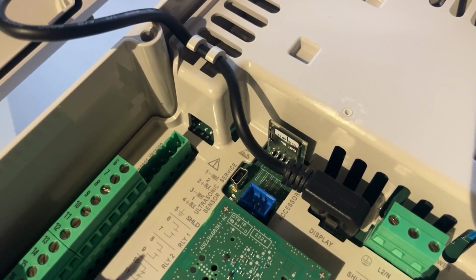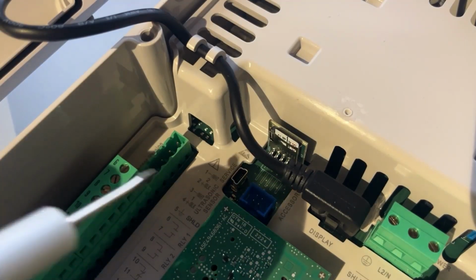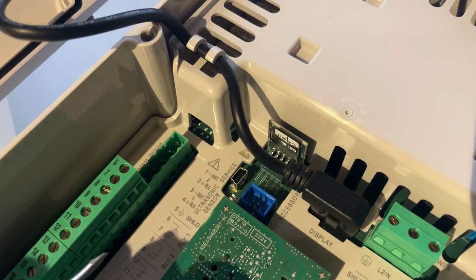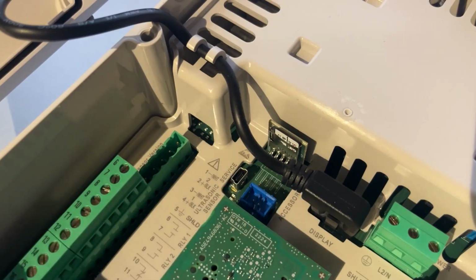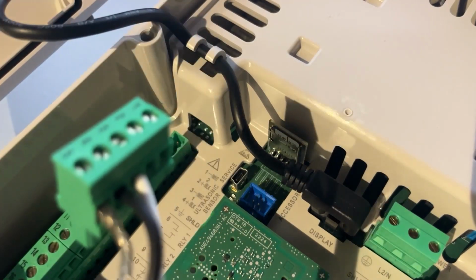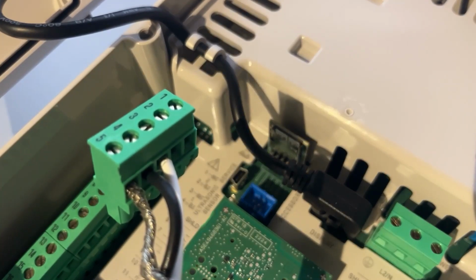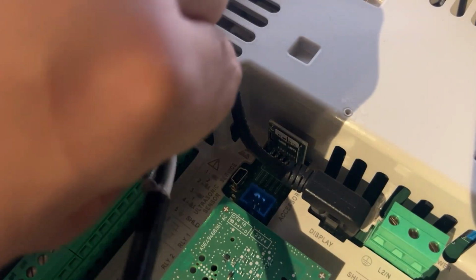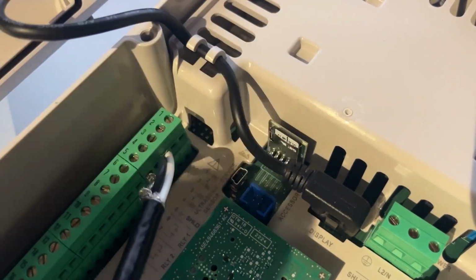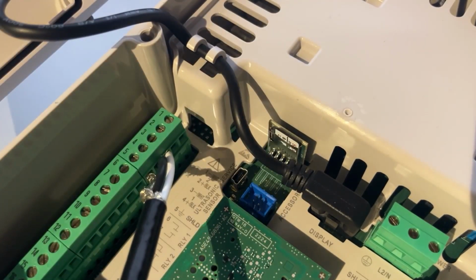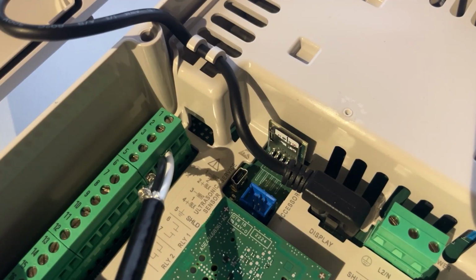So when I go to connect my sensor, I can see again that I pulled the terminal block off, and that it clearly identifies what color the cables are, what point 1 is, what point 2 is. And I have gone and connected my sensor here, so you can see white in 3, black in 4, and then shield in 5. And I'm just going to then plug that in. Very quick and easy to wire. Make sure sensor point 1 is in terminals 3 and 4, just as a quick reminder. But now my transducer is connected, so I can go ahead and power the device.